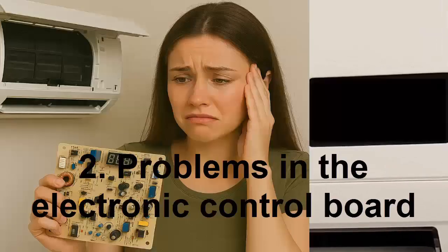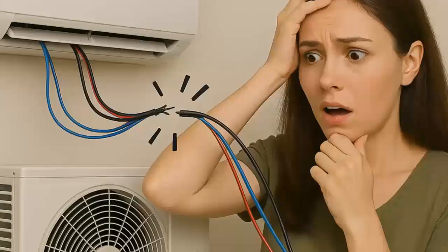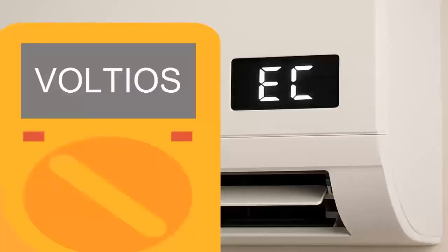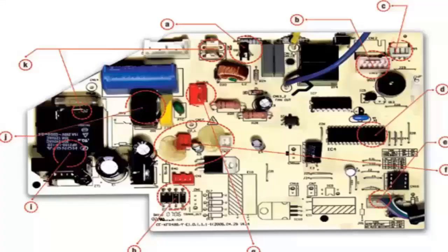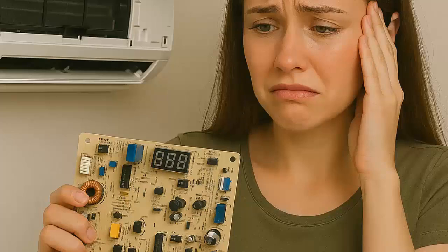Meaning number 2 of code EC is related to electronic control board problems. In many cases, this includes communication errors between indoor and outdoor units, voltage surges from the external power supply, damaged components on the board, such as the compressor relay in non-inverter units. If this relay fails, power won't reach the compressor.